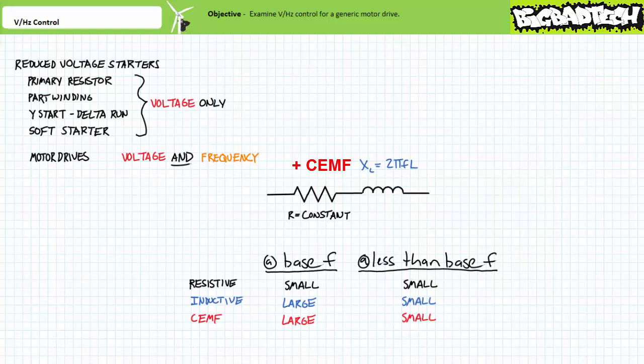This ideal scenario breaks down when an AC source with a reduced excitation frequency and the same voltage magnitude is applied to the motor windings. Assuming the same 120 volt magnitude across each winding at one-tenth the base frequency — or six hertz — is applied, the source not only experiences one-tenth the inductive reactance, but also one-tenth the CEMF because the generator action is weaker at lower speeds. In this case, the source effectively sees only the small resistive opposition and current spikes. The motor quickly enters overload conditions or straight up bursts into flames. In summary, given fixed voltage magnitude at low frequency, opposition is too low and current goes way too high.